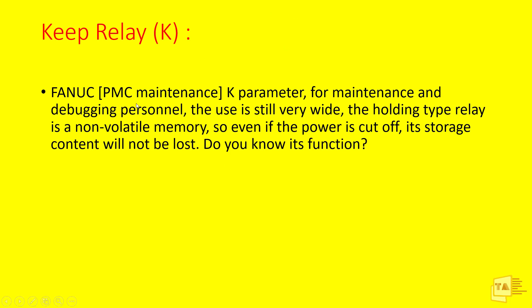The Keep Relay in FANUC is called the K Parameter. Some people call it K Parameter, some call it Keep Relay or bypass relay. For this video I'm using the term K Parameter. This K Parameter is used widely for maintenance and debugging purposes. The Keep Relay is a holding-type relay — it is a non-volatile memory. So even if the power is cut off, its stored content will not be lost. If you enable some Keep Relays while running the machine and the machine shuts down, when you turn it back on the Keep Relay data will retain its previous values.